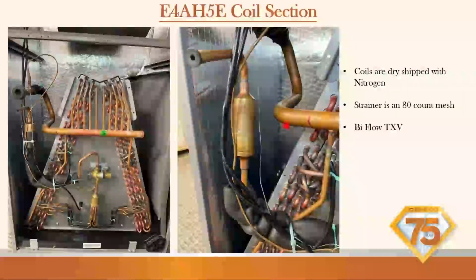Oh, that's a bi-flow TXV, so it's got a little bypass in there. So in AC, we are using the TXV for cooling. In heating, refrigerant flows this way and bypasses the metering device. So when diagnosing, if we're in heating mode and it's not working, it is possible our bypass is plugged if our strainer got plugged. So keep that in mind.